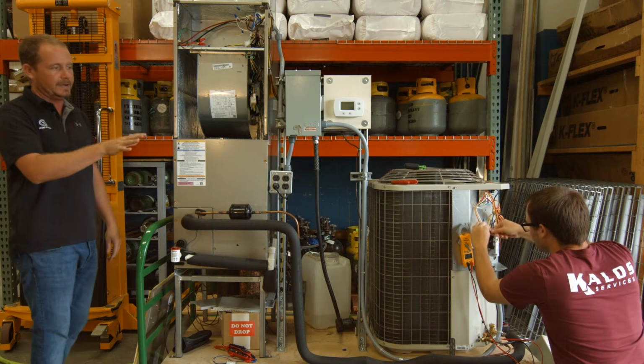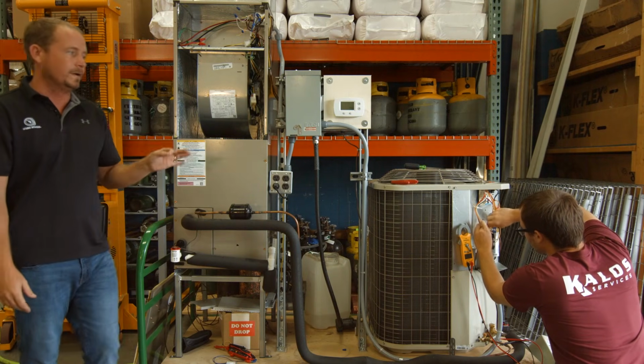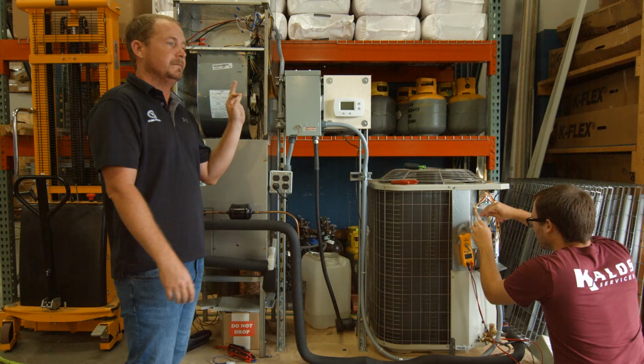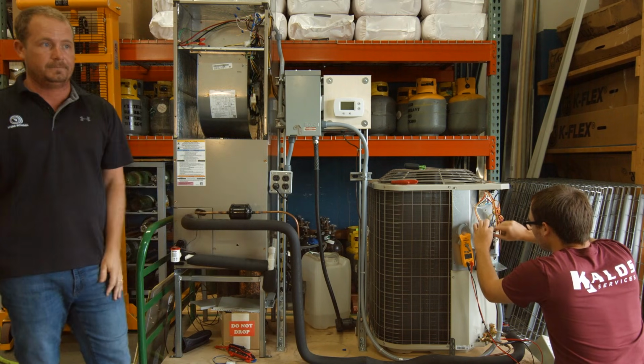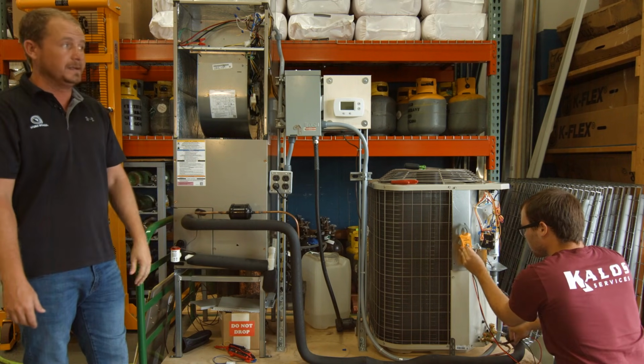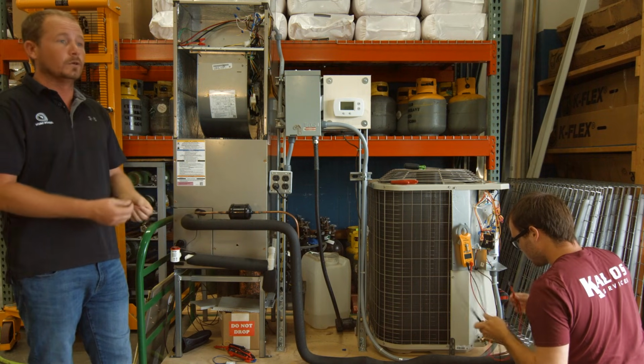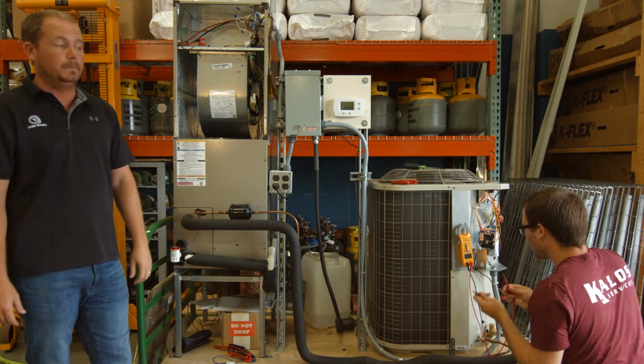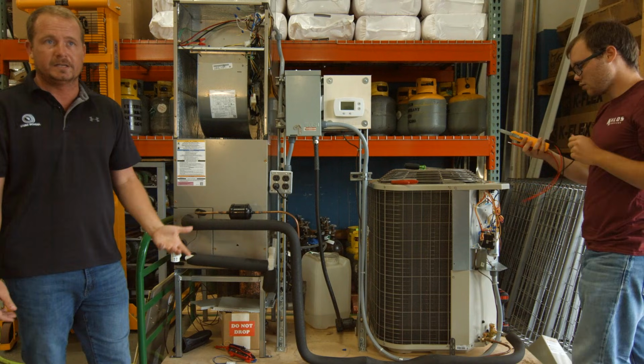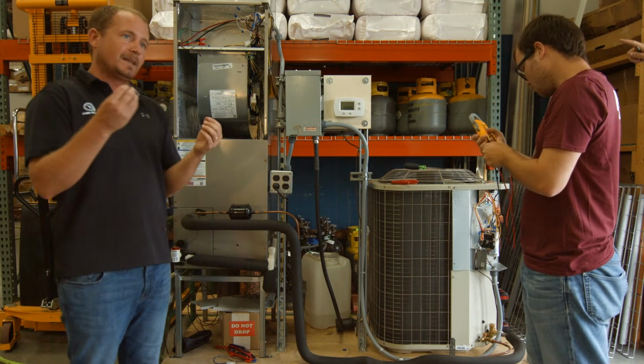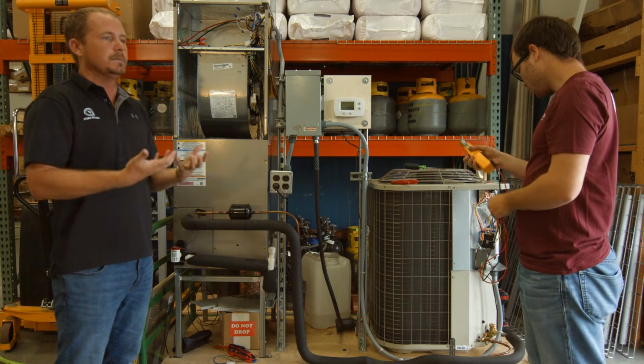But in this case, the diagnosis Tanner made was correct: an open orange conductor between the air handler and the condenser. At that point, your only option would be to either rerun a whole new wire or utilize a different conductor. In some cases, that's your only real choice. But generally, if you've got one conductor compromised, it's only a matter of time.